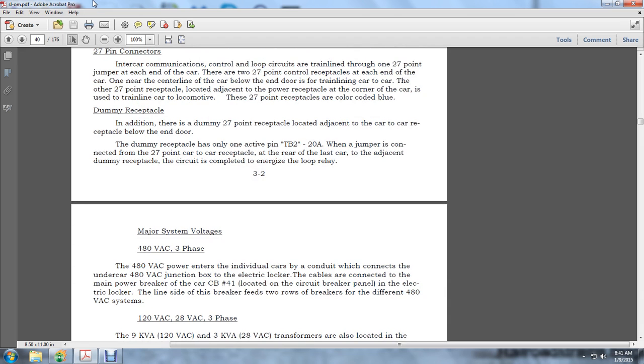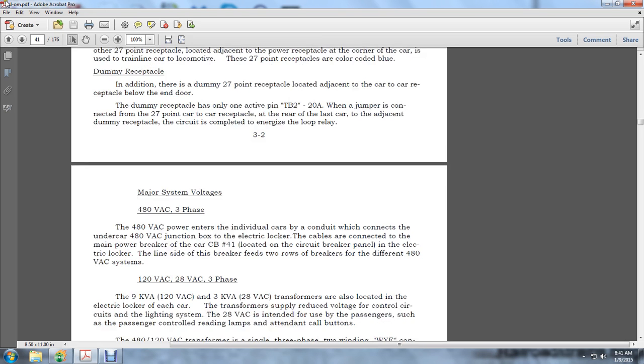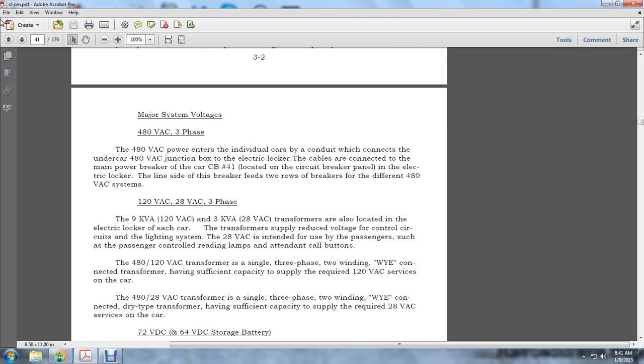Major system voltages: 480 VAC 3-phase. 480 VAC power enters the individual car by conductors to an undercar 480 VAC junction box in the electrical locker. The cables are connected to the main power breaker on the car. The CB number 41 is located on the circuit breaker panel in the electrical locker. The line side of the breaker feeds two rows of breakers for the 480 VAC system. The 120 VAC and 28 VAC systems, 3-phase, 9 kVA for the 120 VAC and 3 kVA for the 28 VAC transformers, are located in the electrical locker of each car.